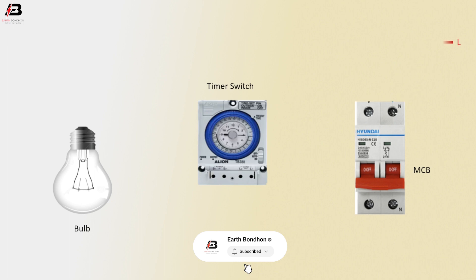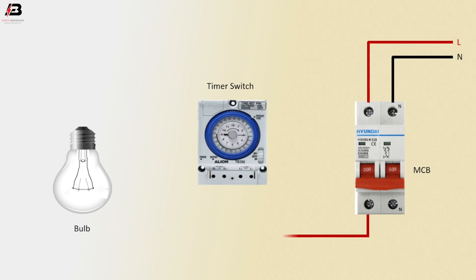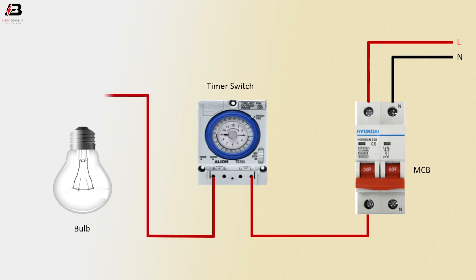Phase connection input to double pole MCB circuit breaker. Neutral connection input to double pole MCB circuit breaker. Phase connection outgoing from MCB circuit breaker to connect timer switch. Phase connection outgoing from timer switch to connect bulb phase point.